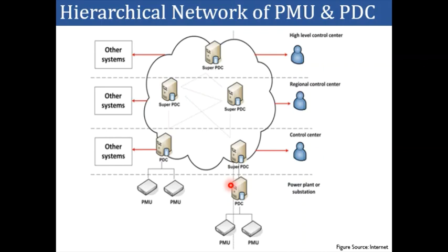What is the role of the phasor data concentrator? The phasor data concentrator takes the data of different PMUs and time aligns their phasor data so that we get one single snapshot of the data set provided by the PMUs. So the main role of the PDC is to time align the data and filter out the measurement data which is coming from the field.